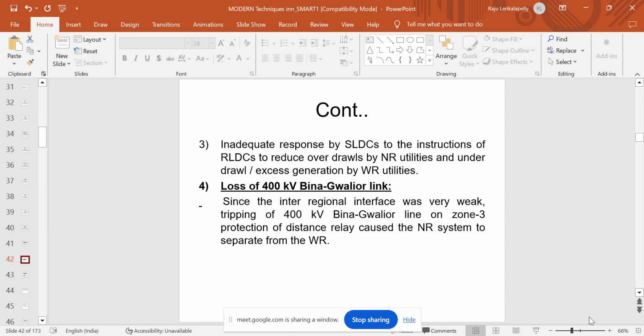The fourth point is the loss of the 400 kV Bina-Gwalior link. From a protection standpoint, distance protection has zone 1, zone 2, and zone 3 protection. Because of overloading, zone 3 protection mal-operated. This is also one of the reasons.